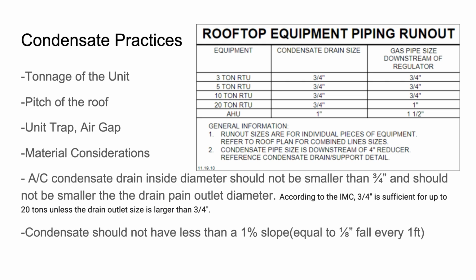So this is just the basic outlook, is if you were running one drain to each of these units, this is what you would have to go with. It looks pretty much about 3/4 all the way, except for an AHU, which can be a 20, 30, or, well, I haven't seen a 20, but a 30 or 40 ton would be a 1 inch. It also happens to have gas lines for downstream of the regulator as well. You got to know the tonnage of the unit. You got to know how many units you're actually tying into the same drain line.